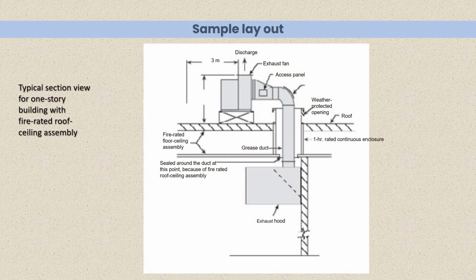This is the one layout I have inserted here. This is not part of the standard. You can see the layout of typical section view. This is a typical section view for one-story building with fire rated roof assembly. So you can see the 1 hour rated continuous enclosure. Enclosure is mainly duct is passed through that enclosure, and that enclosure is sealed from top and bottom.